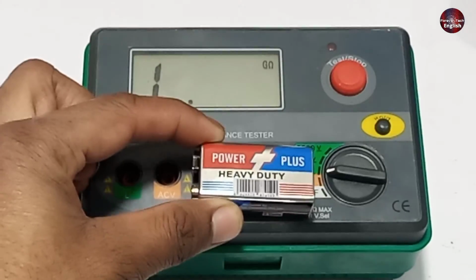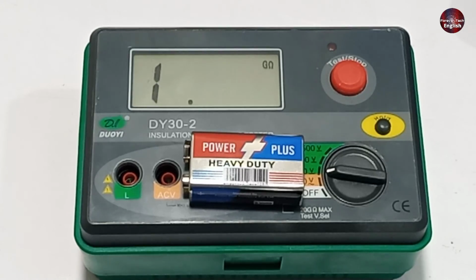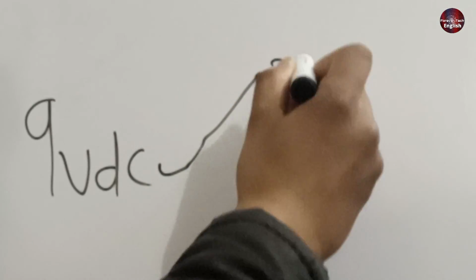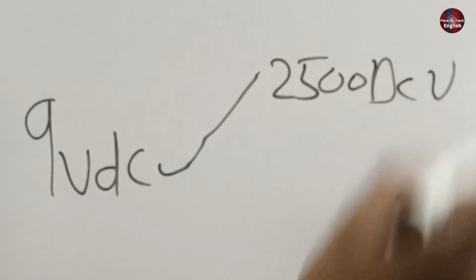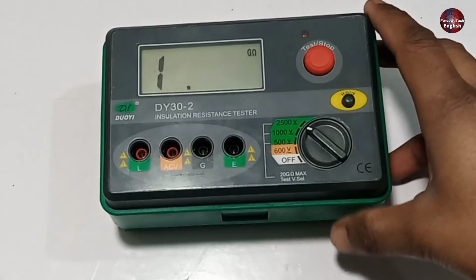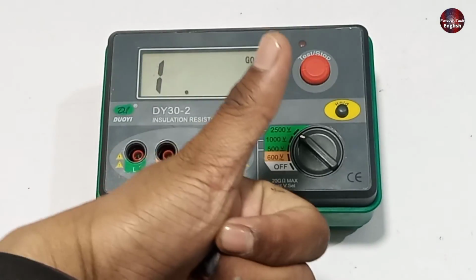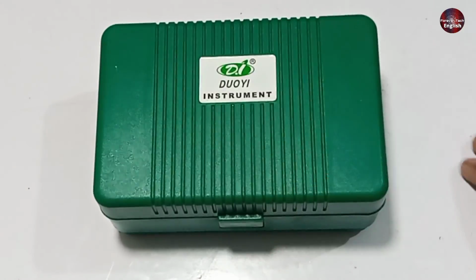As this insulation tester also has a 9-volt battery. But it amplifies 9 volts to high voltages. This makes the testing with the insulation tester more accurate and tells us that the insulation is good. And this is how you test using an insulation resistance tester.